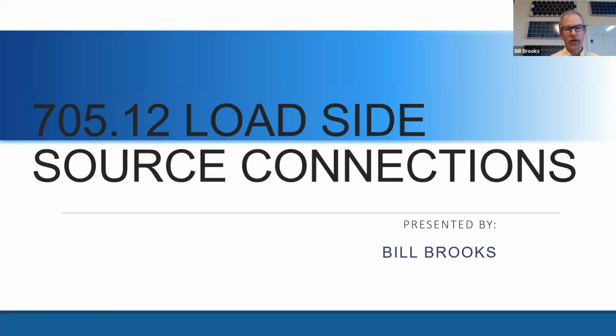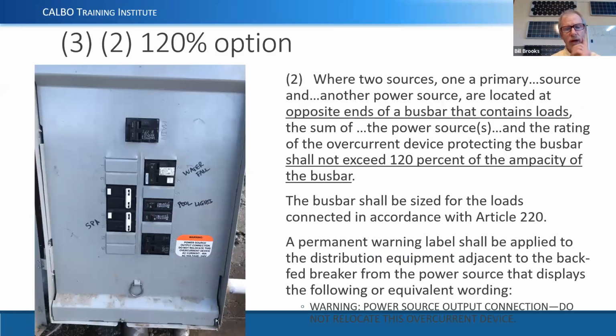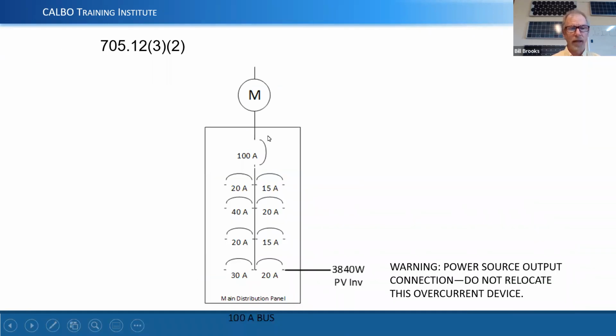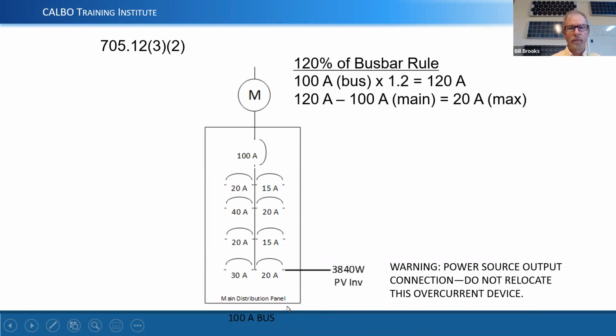Okay, load side source connections. See, I'm just going to hit these. This is super quick. The 120% rule basically is not the only rule, but it has certainly been the most used of all the rules. And that's where we say don't relocate the overcurrent device. We have the main breaker coming in here, and then the PV system at the opposite end. And so that's, you know, on 100 amp service, it's only a 20 amp PV system that you can put in, which is a maximum of 3,840 watts.